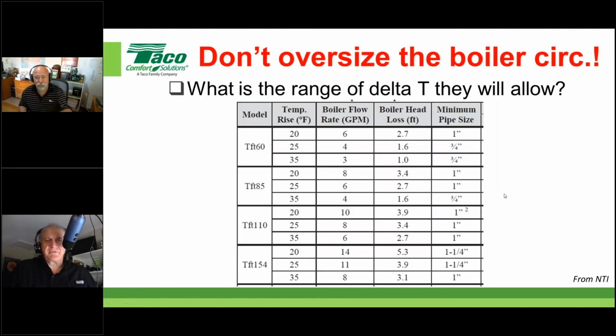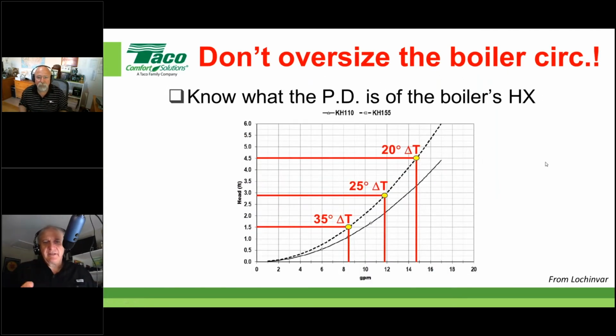Could you go back one slide real quick, Rick? I just want to make sure everybody understands that. Here we're talking at a 35-degree delta T. The boiler pump needs to deliver, in this case, 8.5 gallons a minute, but the head loss through the heat exchanger is only 1.5 feet.